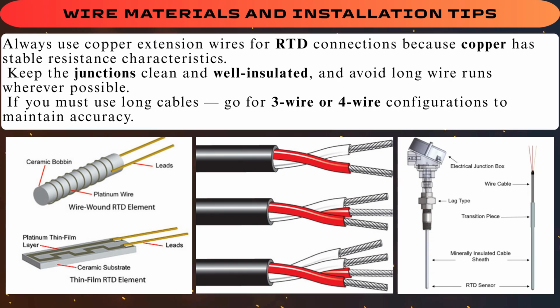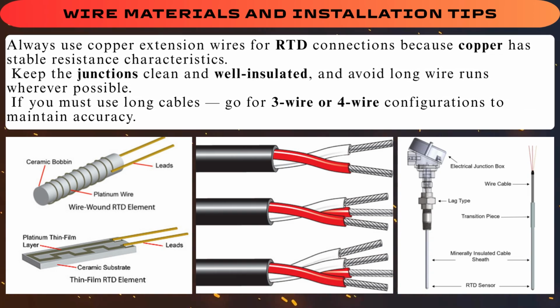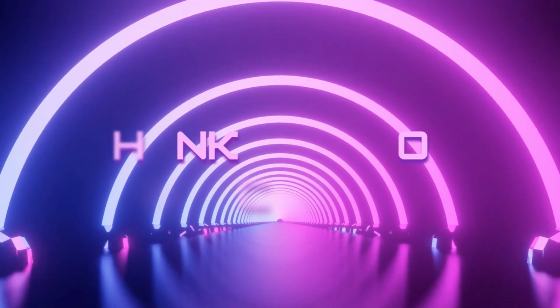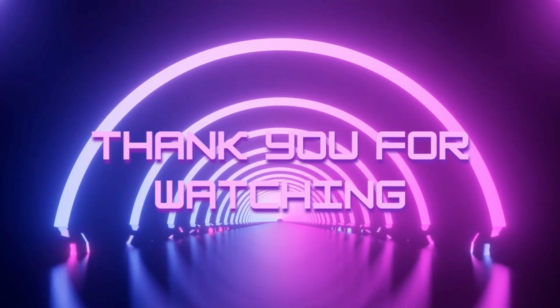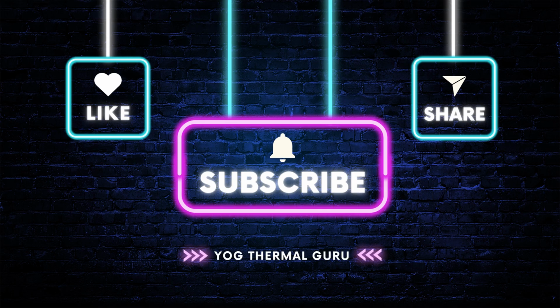Wire materials and installation tips. Always use copper extension wires for RTD connections because copper has stable resistance characteristics. Keep the junctions clean and well insulated and avoid long wire runs wherever possible. If you must use long cables, go for 3-wire or 4-wire configurations to maintain accuracy. So that's the complete explanation of 2-wire, 3-wire and 4-wire RTD connections, how they work, where to use them, and which one gives the best accuracy.